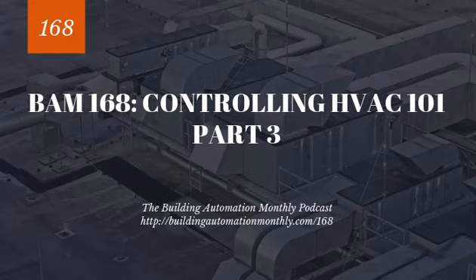Now, as the temperature continues to increase, we will typically turn on the tower fans and send water over the tower. We're taking advantage of the evaporative effect by doing that. So that's the big thing we need to realize when we are controlling water through the tower. Now, there's all sorts of things of water starvation and unequal sumps and things like that. I'm not really going to dive too much into that.